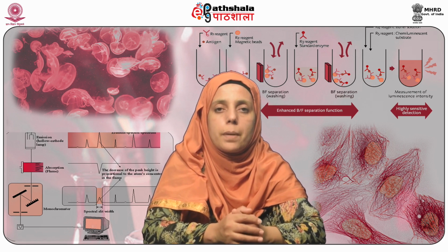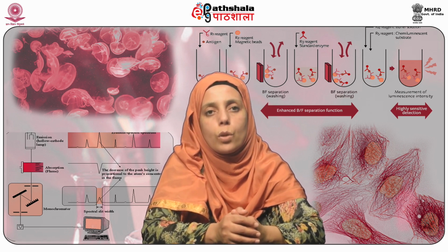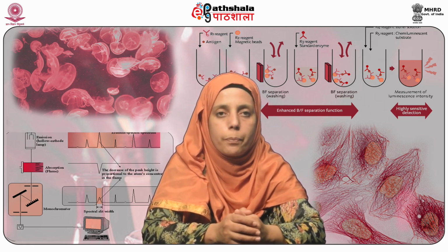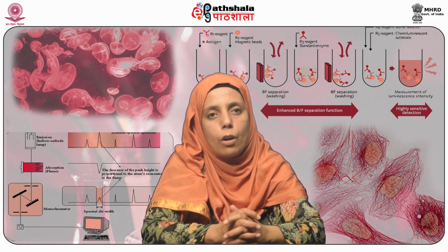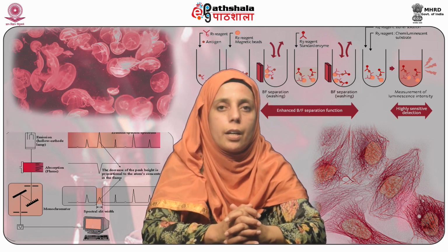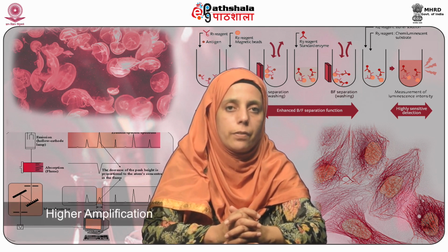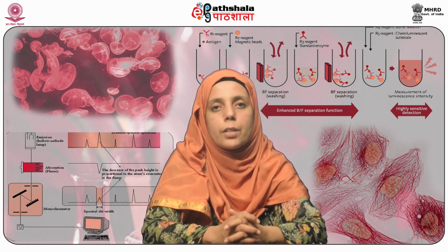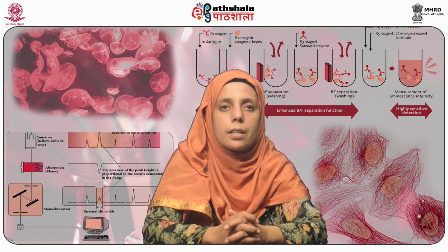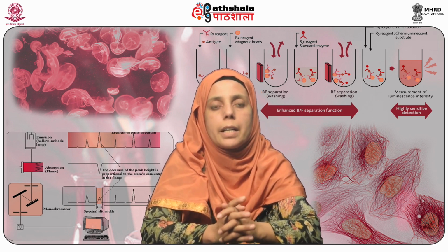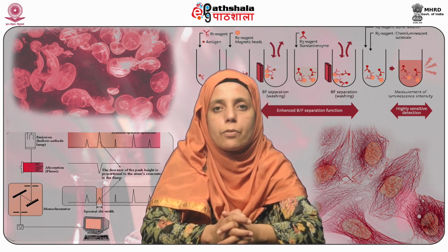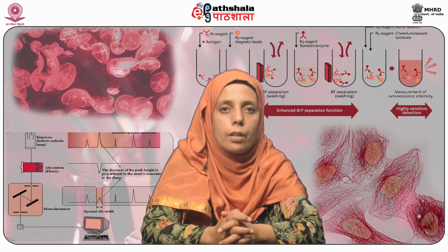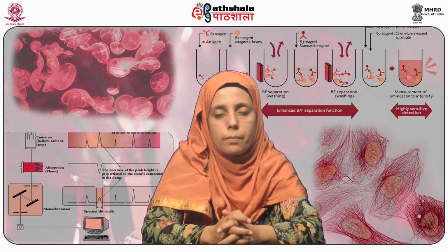The size of this pulse depends upon the overall voltage applied to the PMT. The higher the voltage, the higher the number of electrons ejected from each dynode, and hence higher amplification. For quantitative measurements, the anode current must be proportionate to the light intensity. A non-linear response can result from an excessive current being drawn from the photocathode.